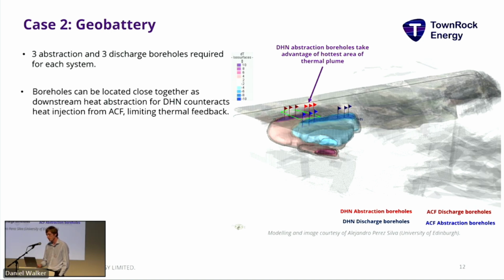We need 3 abstraction and 3 discharge boreholes for each system, so 12 in total. We want those boreholes located fairly close together, because you want the thermal plume created by the cooling to be picked up by the heating scheme - a kind of thermal feedback, if you like.